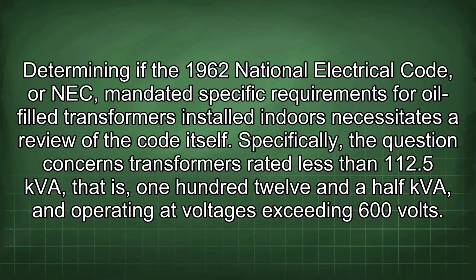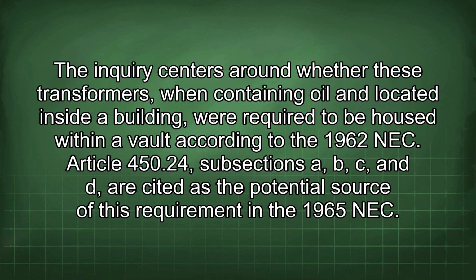Determining if the 1962 National Electrical Code, or NEC, mandated specific requirements for oil-filled transformers installed indoors necessitates a review of the code itself. Specifically, the question concerns transformers rated less than 112.5 kVA and operating at voltages exceeding 600 volts. The inquiry centers around whether these transformers, when containing oil and located inside a building, were required to be housed within a vault according to the 1962 NEC.